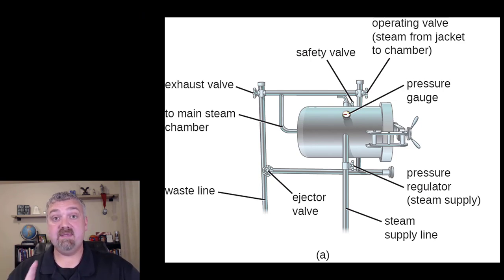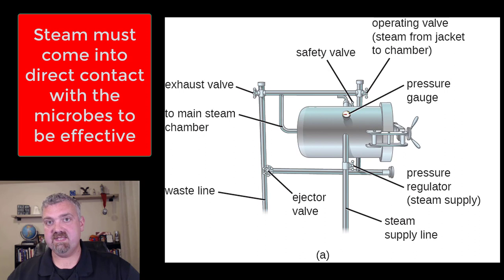Now the second key thing with the autoclave besides 121 degrees, 15 minutes, 15 psi is how they work. Steam is what's killing and sterilizing the organisms inside this chamber. But steam must come into direct contact with what's in the chamber.